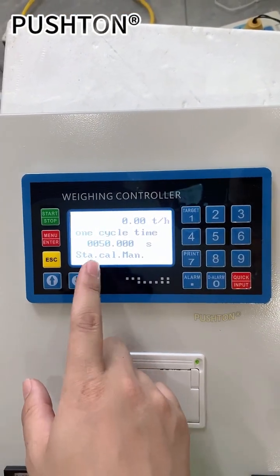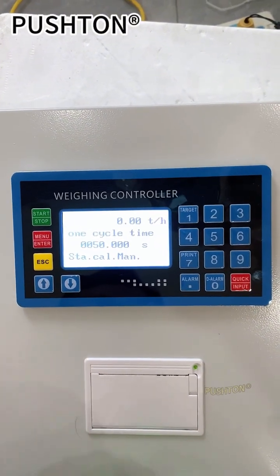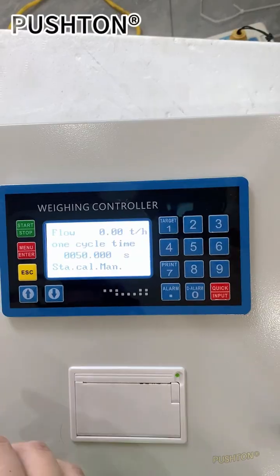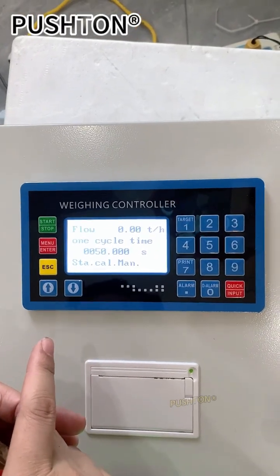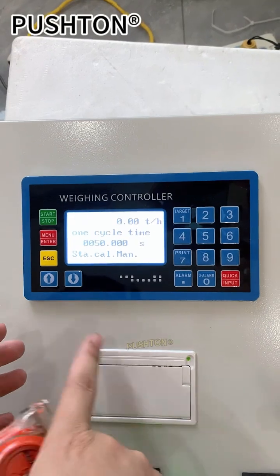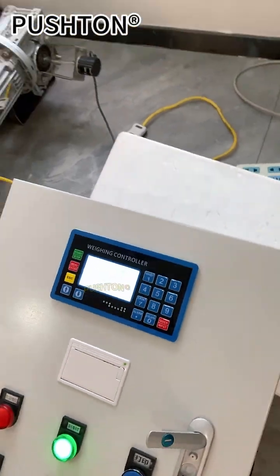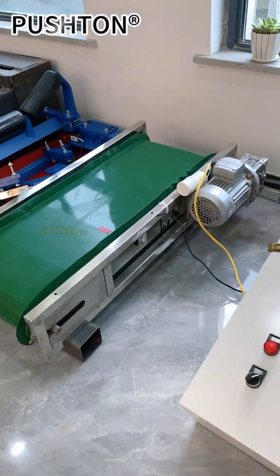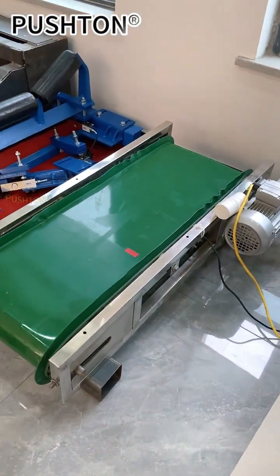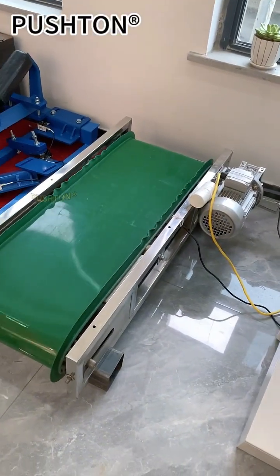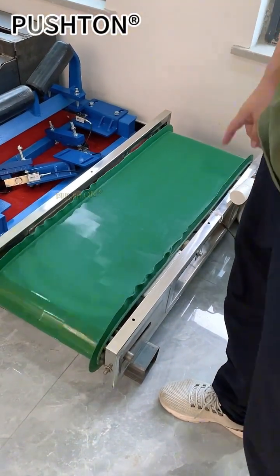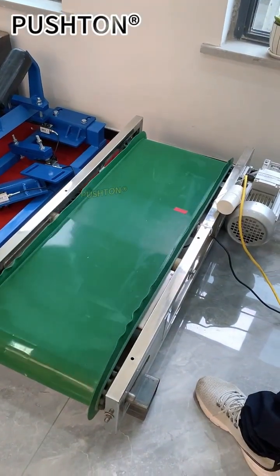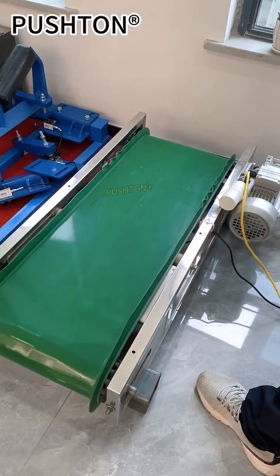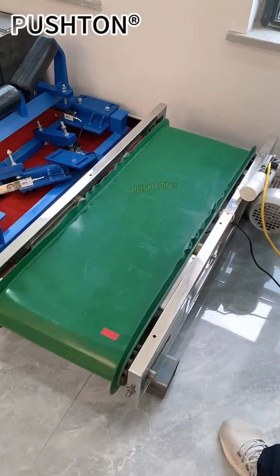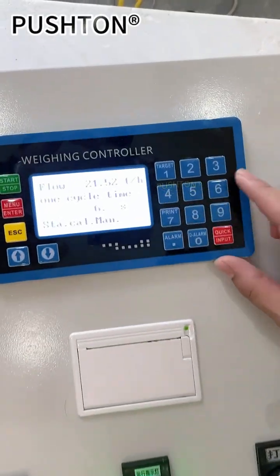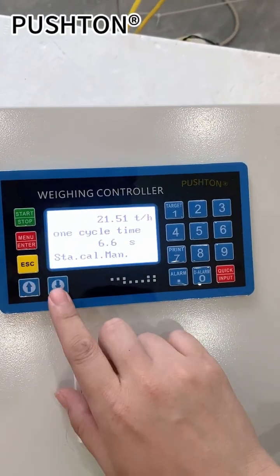At this time, we need to measure the time for the belt to rotate once. In the case of a frequency converter, adjust the frequency converter to 50 Hz. If not, then don't worry about it. Set the belt to the highest speed, with the belt idling. Make a mark on the belt, then use a stopwatch to time how long it takes to rotate once. My belt rotates once in 6.6 seconds. Just enter 6.6 directly. Enter.